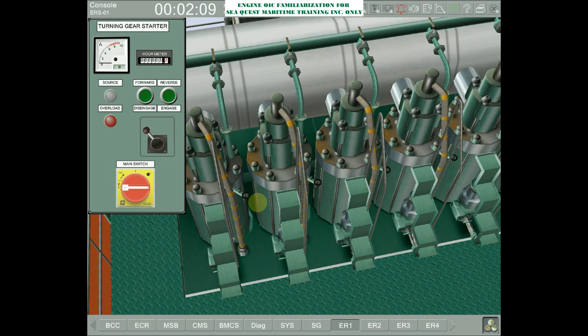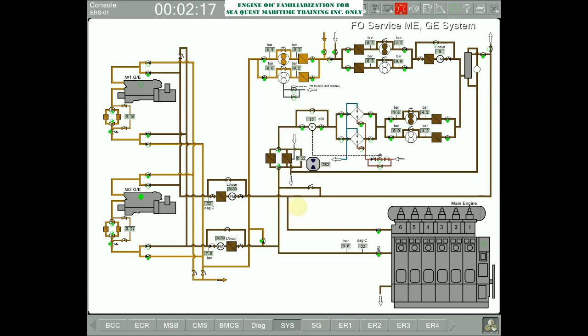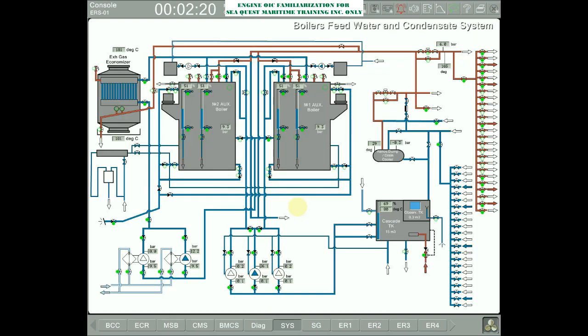Okay. Then go to SYS, select boiler feed water and condensate system. Make sure that the number 1 boiler steam outlet valve is open. Sometimes in some scenarios it is closed. So just to be sure that the valve is open, go to SYS and boiler feed water and condensate system.